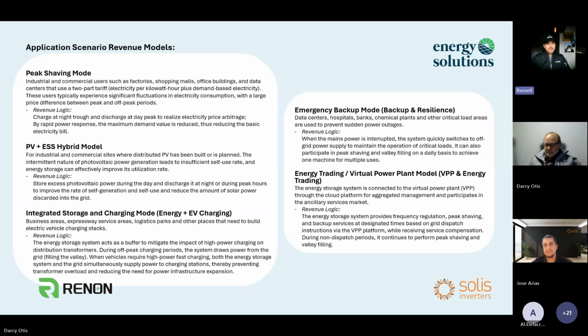There's also some applications where you'll see shifted cost between high demand and low demand time for cost of energy. For example, overnight 1 a.m. to 5 a.m. might be 17 cents a kilowatt hour, whereas from 5 p.m. to 9 p.m. it's something like 35 cents a kilowatt hour. So in that peak shaving mode, there's also an opportunity for pure energy arbitrage.